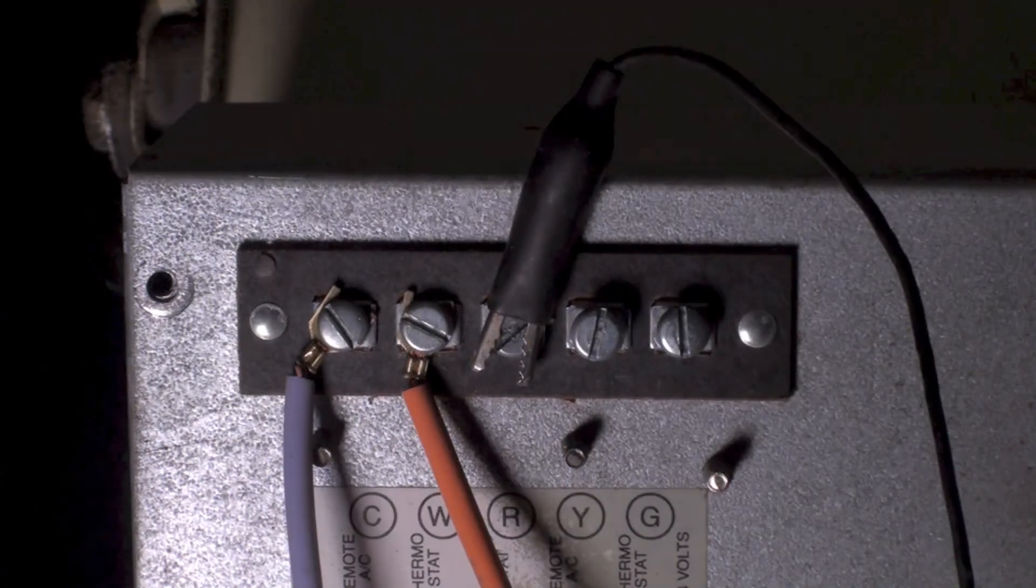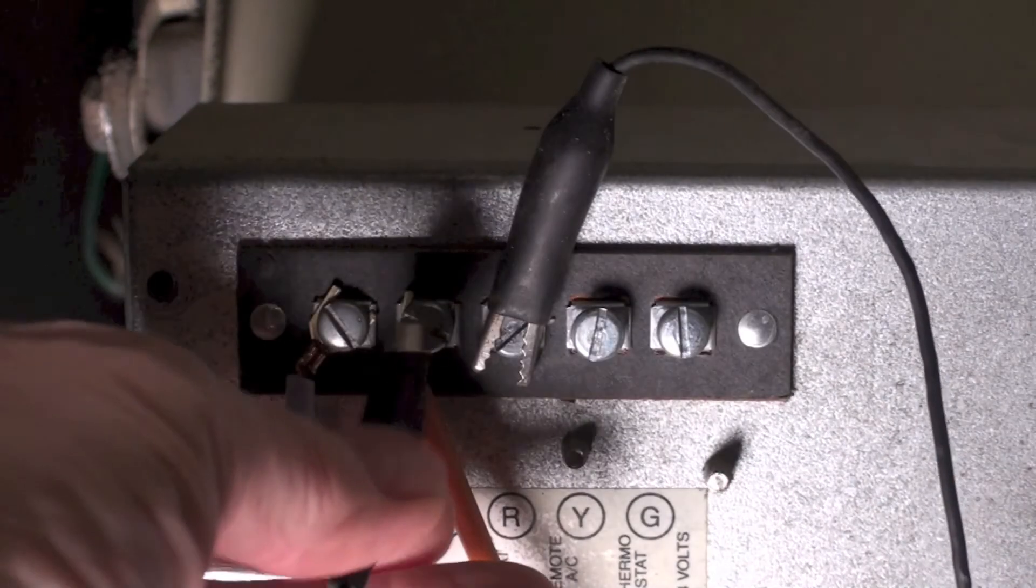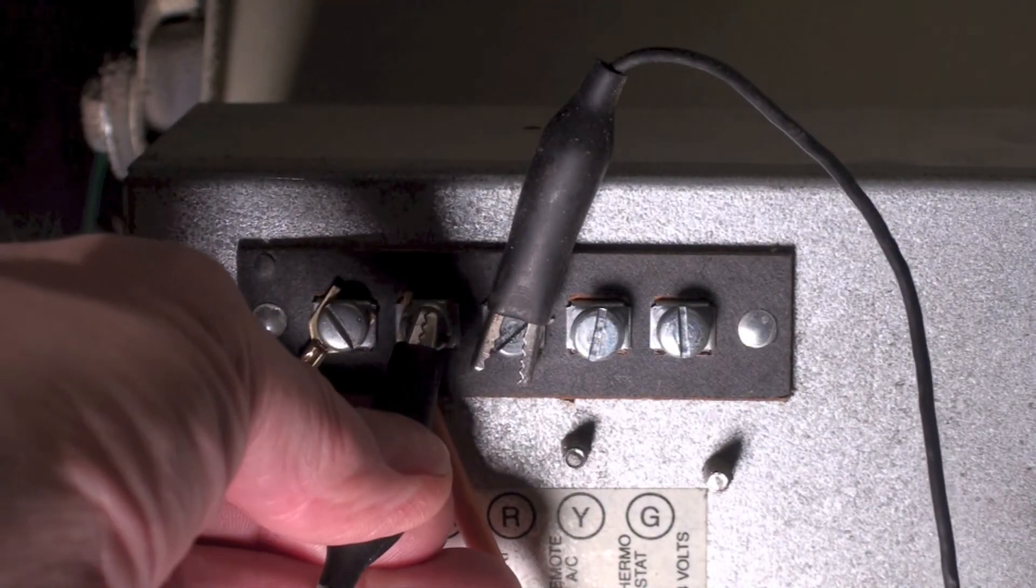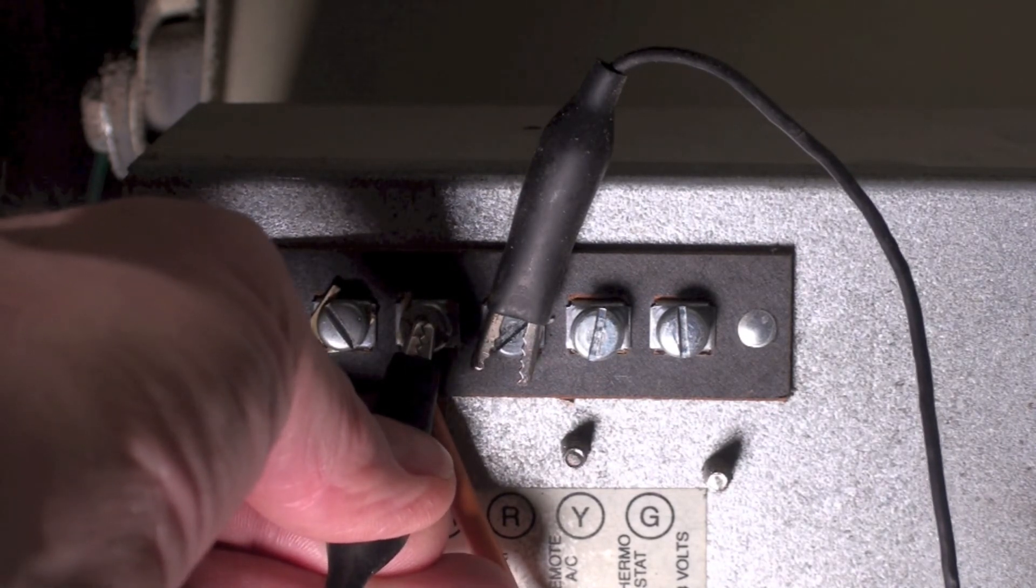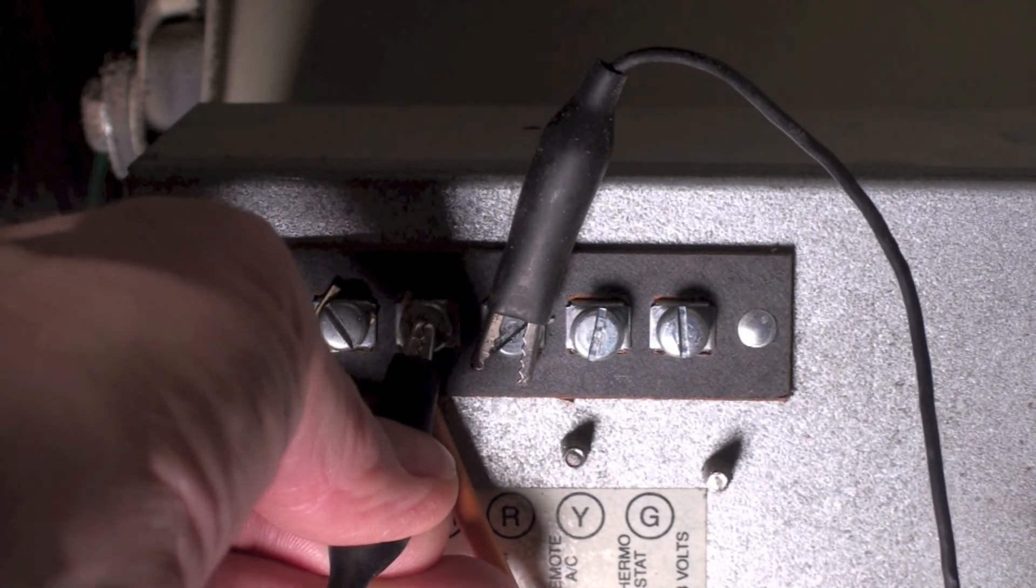Now, if you jumper from R to W, you can hear that - that's the forced blower, combustion blower coming on.